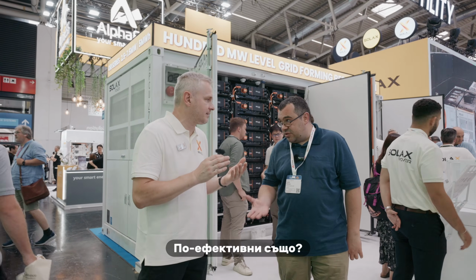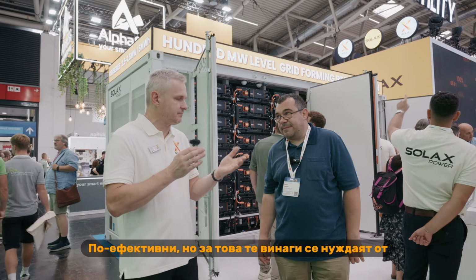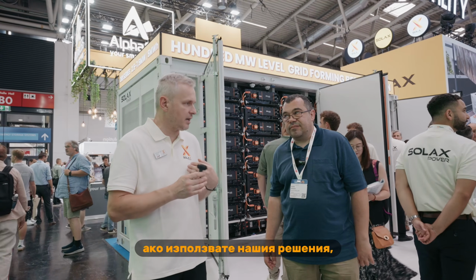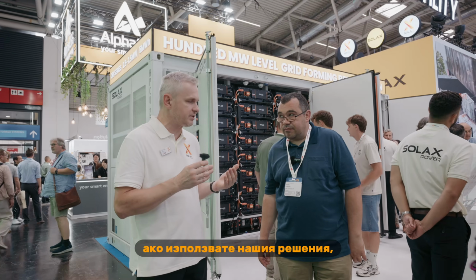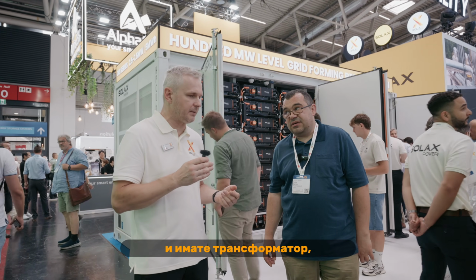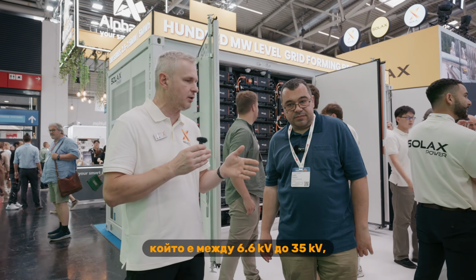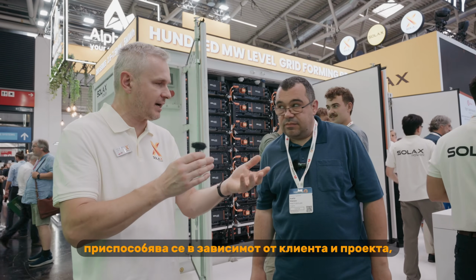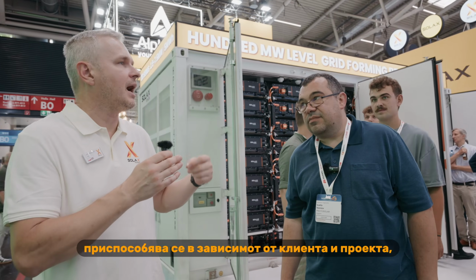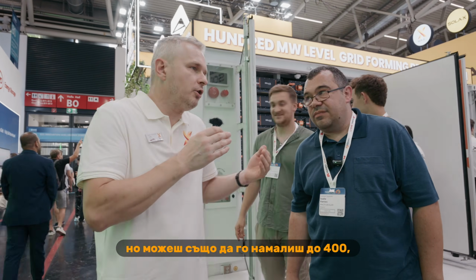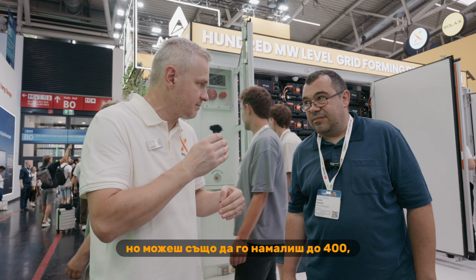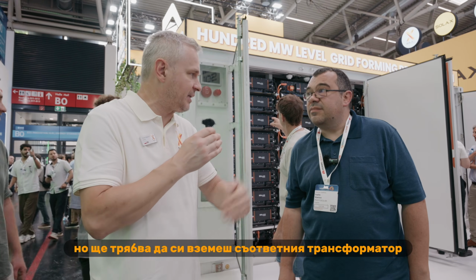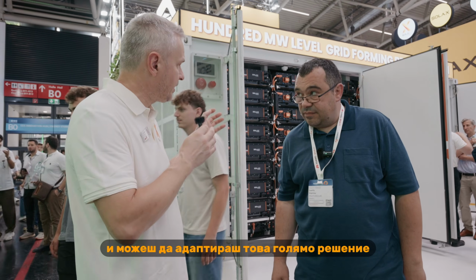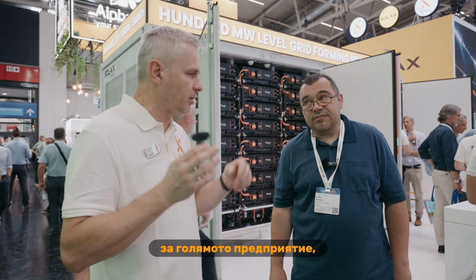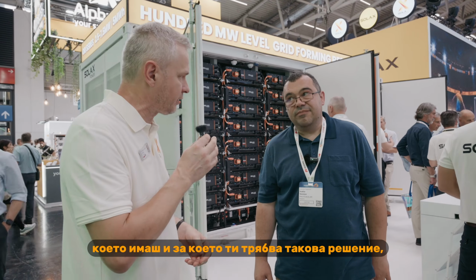More efficient too? More efficient, but that's why they always need a transformer. If you're using our dedicated solutions, you have a transformer to step up to the middle voltage, which is from 6.6 kilovolts up to 35 kilovolts. It's also customized for the customer according to the project. But you can also step it down to 400s, though you'll need that step-down transformer, and you could adopt this big solution for a huge manufacturing plant that needs that kind of storage, let's say 10 megawatt hours.